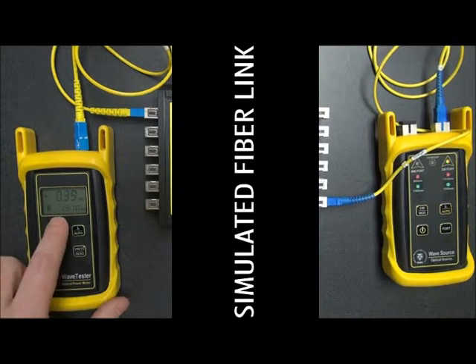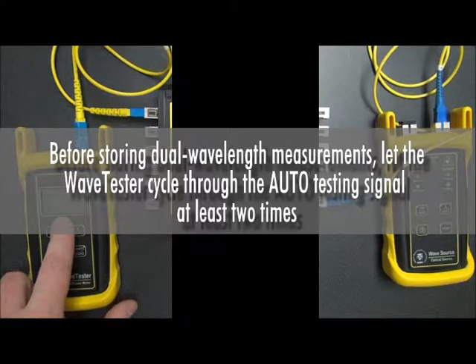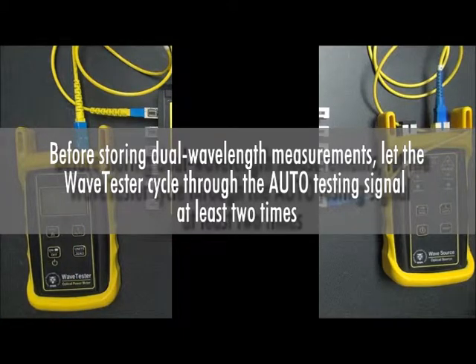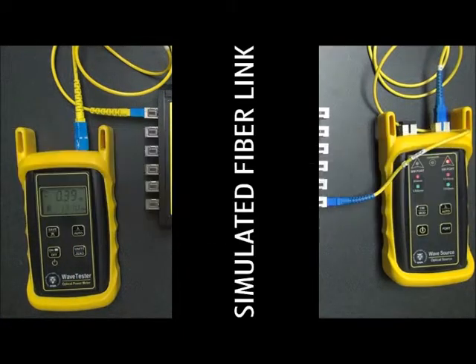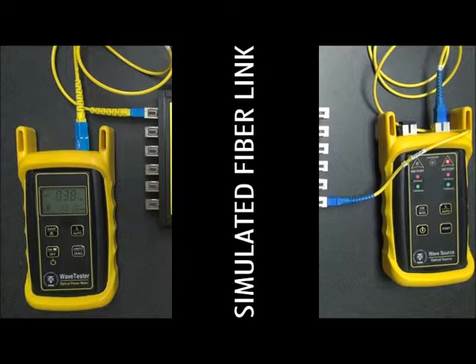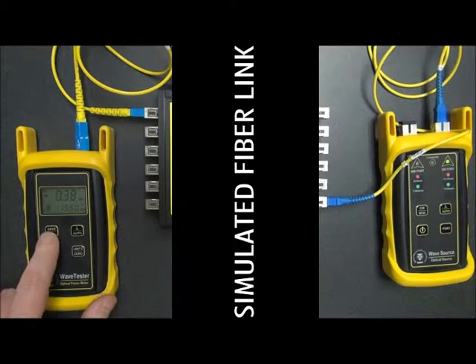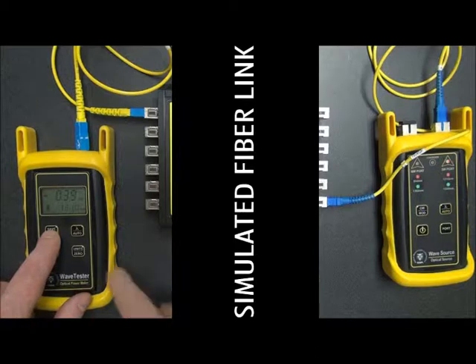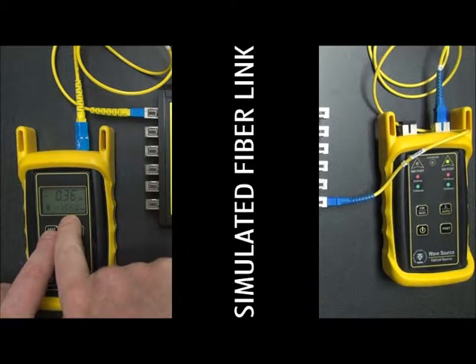What you need to do is watch the WaveTester here. Make sure it goes through a couple cycles of the wavelengths. Once you've done that, now you can press the save button here to store the readings. Now what's going to happen is that because we're taking two measurements, we're in auto mode, we're going to take a 1310 measurement and a 1550 measurement simultaneously. So when I press the save button here, you'll notice that the fiber number will increment by 2.